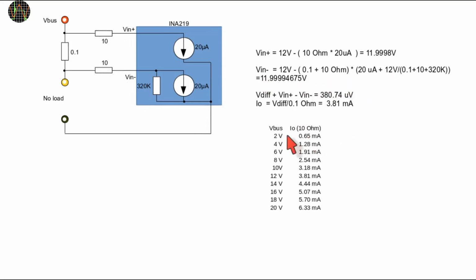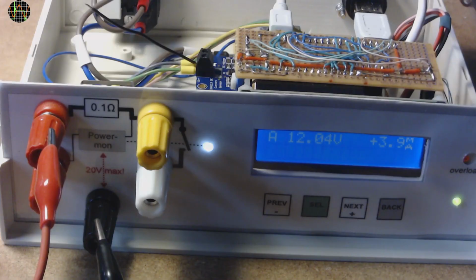So we can expect an offset of 0.65 milliamps to 6.33 milliamps for V-bus ranges from 2 to 20 volts. In this test, a variable voltage supply is connected to the red and black terminals, with no load connected. Changing the bus voltage produced the expected offset current.